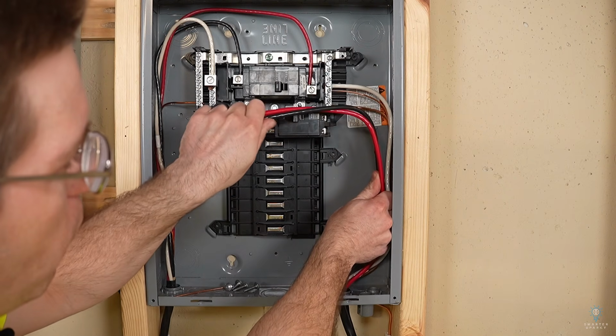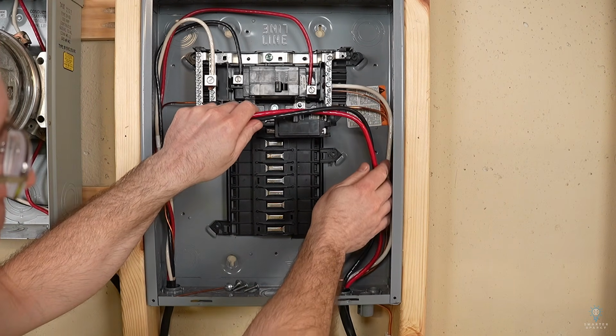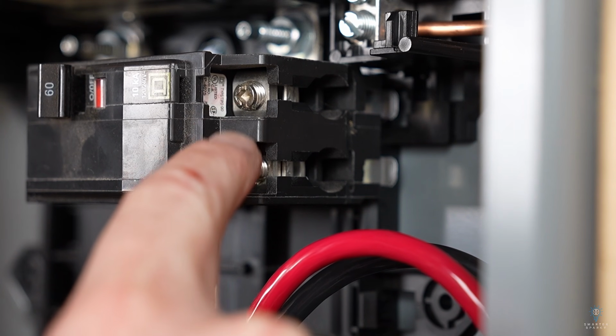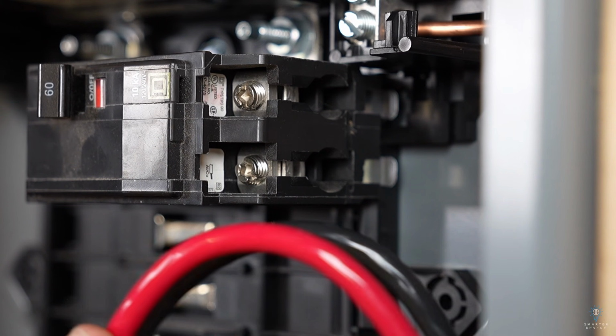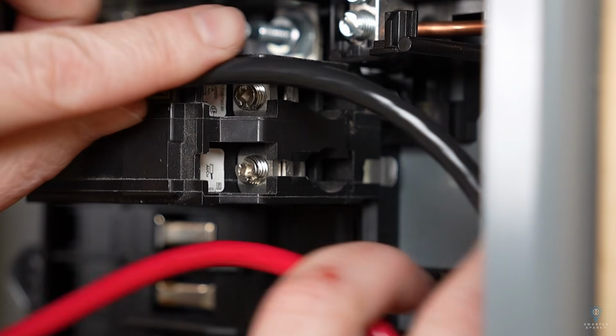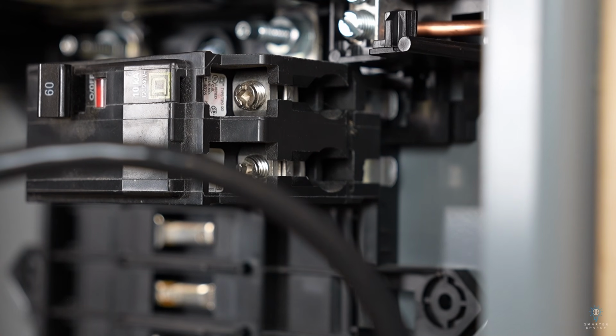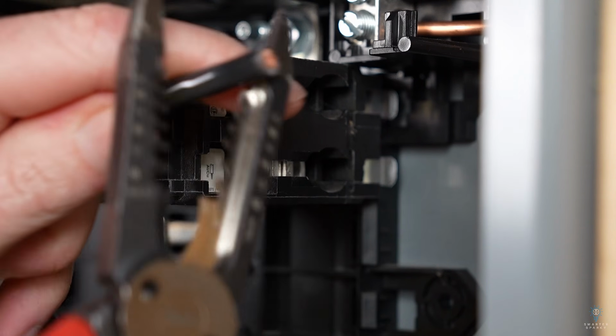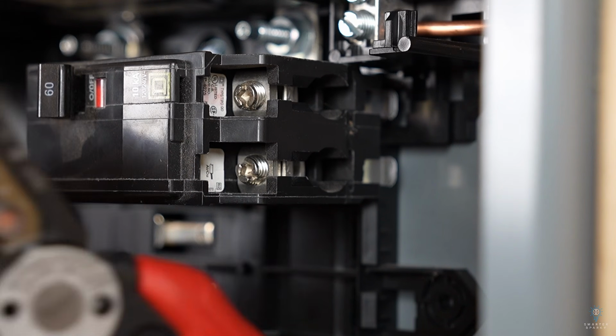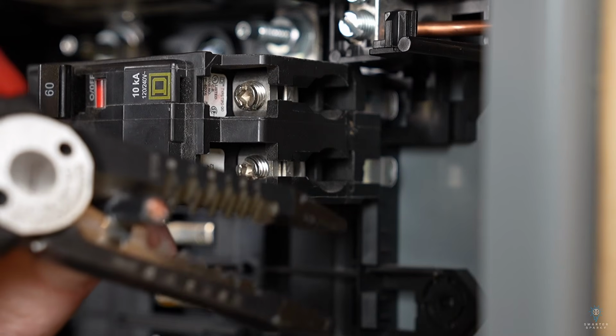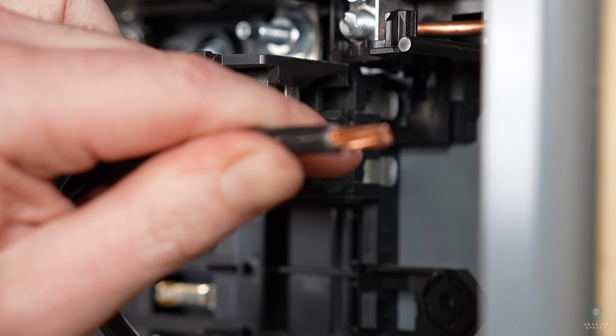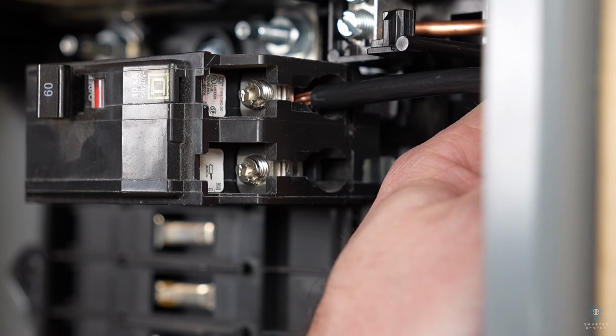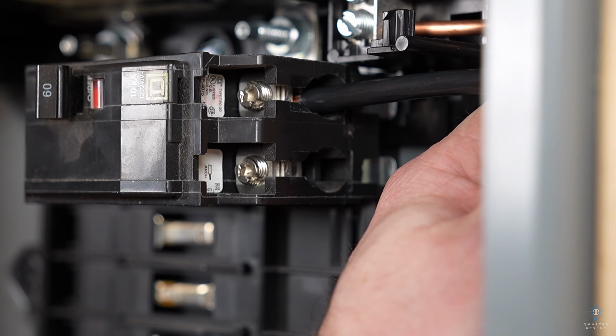So we bend our wires roughly to where we want them, and they are ultimately going to land on these 2 lugs coming out of the breaker. So we want our black on the top, so we'll go ahead, give that a cut, and just like before, we're just gonna score it with the wire cutting portion of the stripper. And these breakers tend to need to be stripped a little shorter than everything else we've done. So there I've maybe stripped out just shy of 1/2 inch. And we should be able to push that in like so.